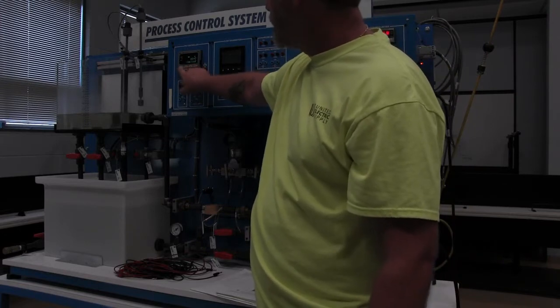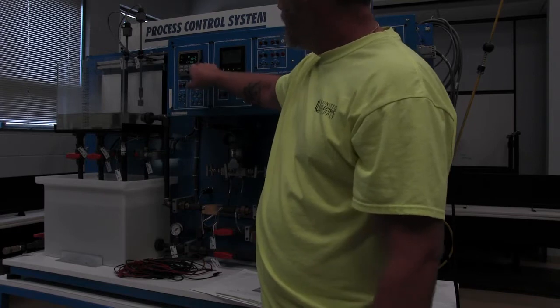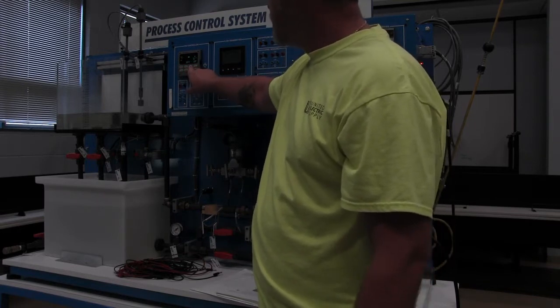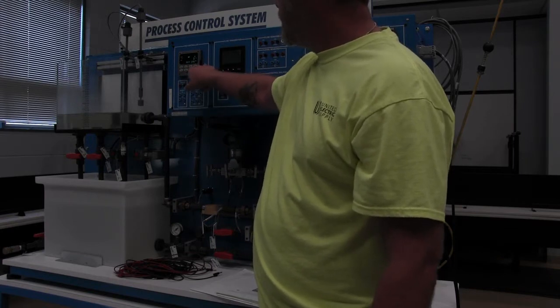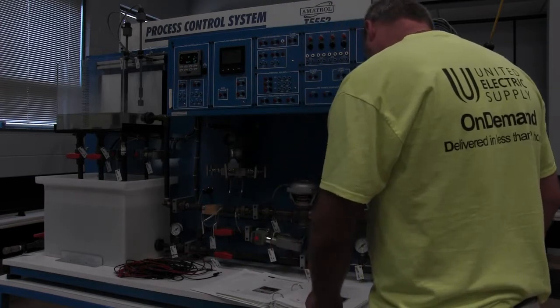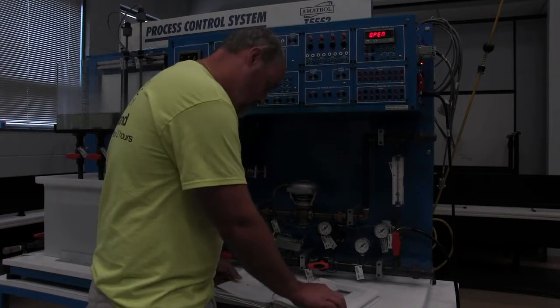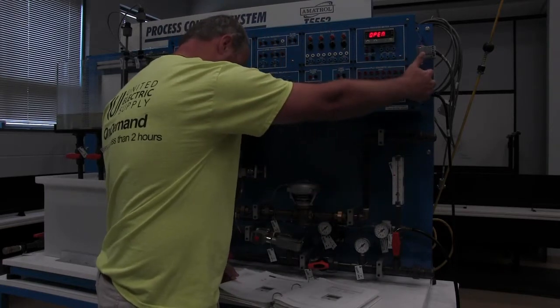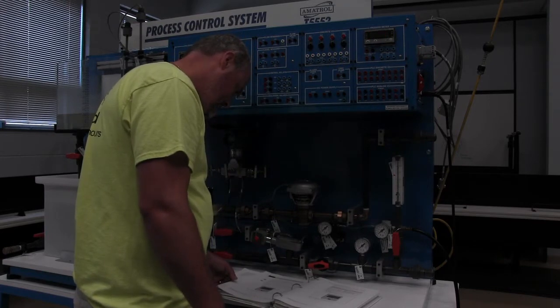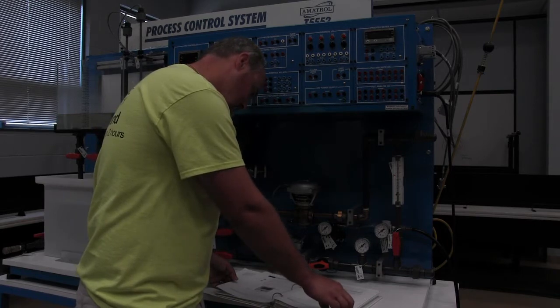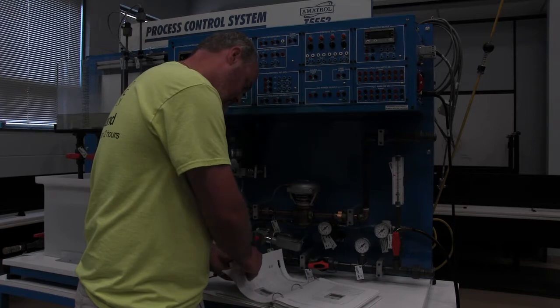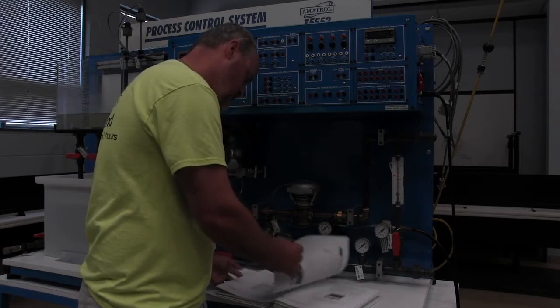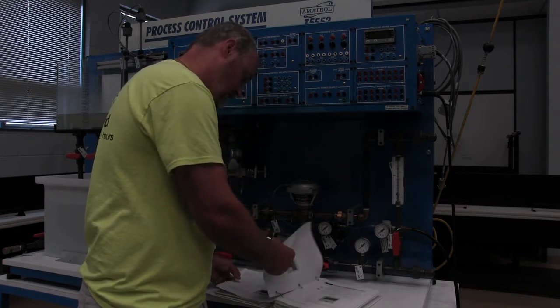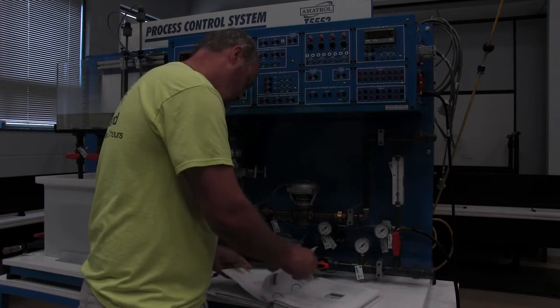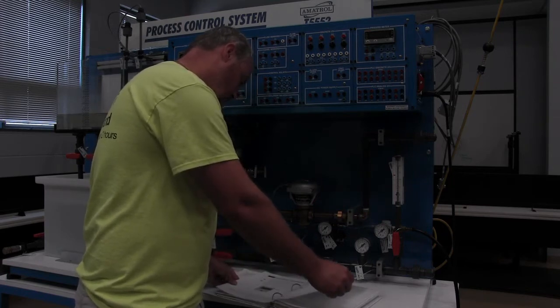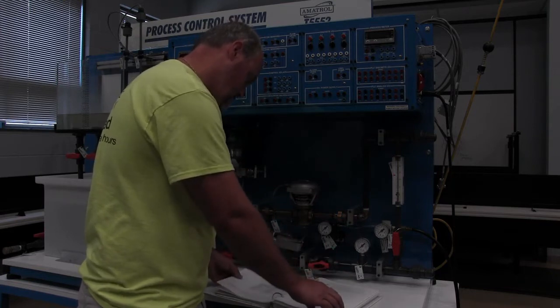Now it wants us to test all the keys. It says function, lower display, auto manual, set point select, setup, increment. So everything worked. We're good to go there. Now it says turn off the main circuit breaker. Then it's just going through the menus of what parameters you can adjust. And we will be going in to adjust a few of these settings shortly.